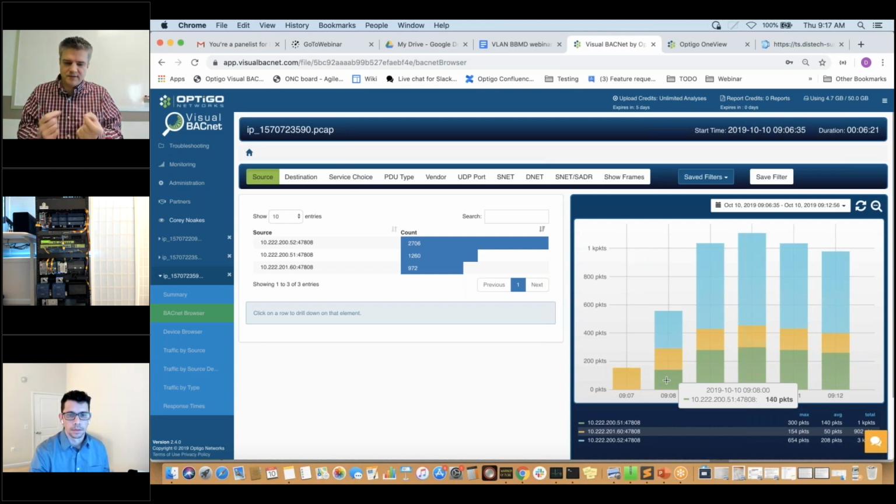So you want to have as few BBMDs as you can, and you want to design your VLANs in a service-oriented way so they don't really need to talk to each other. I think that was the key takeaway from that.